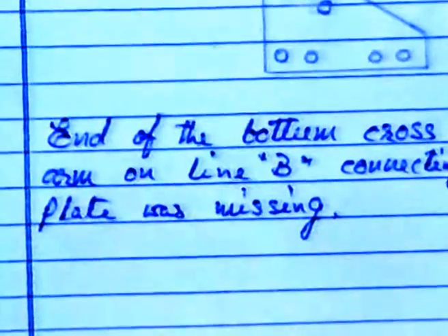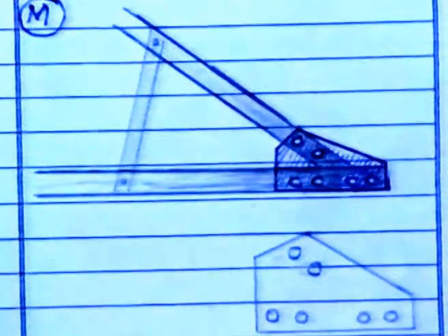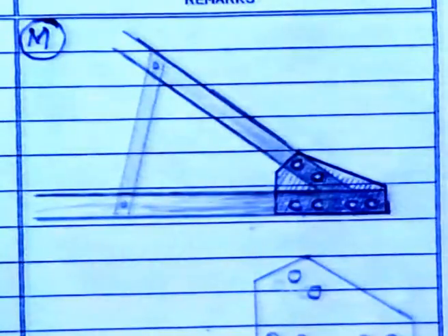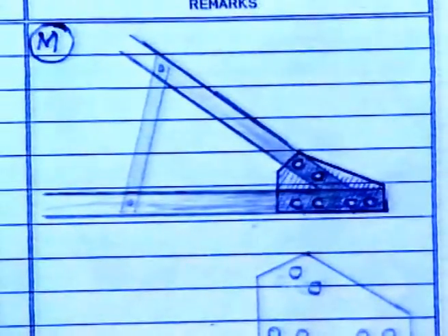The datasheet LMS-3001-01 shall be used for reporting the line conditions. Additional items shall be noted on the remarks section of the form. When recording the conditions, the degree of damage or deterioration shall be adequately described or estimated. An incomplete description may lead to assigning work to a lower priority, thus causing either a safety hazard or a potential forced outage.